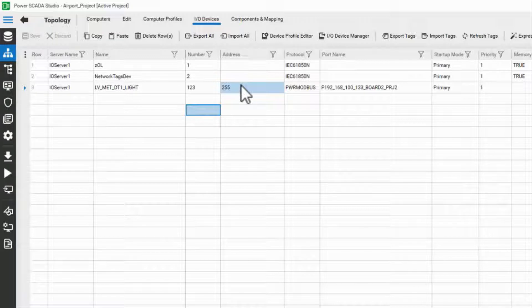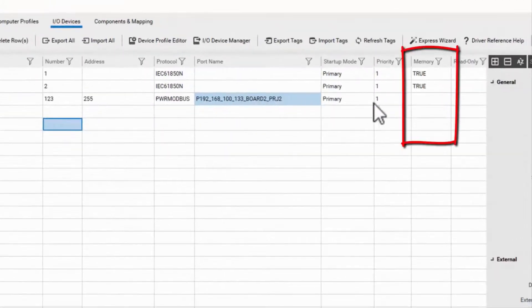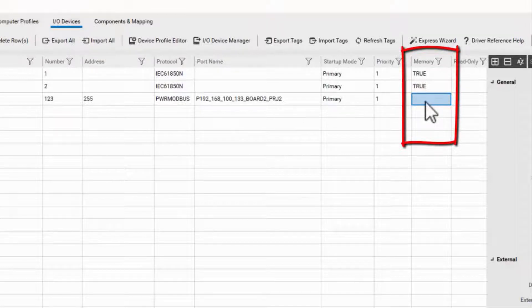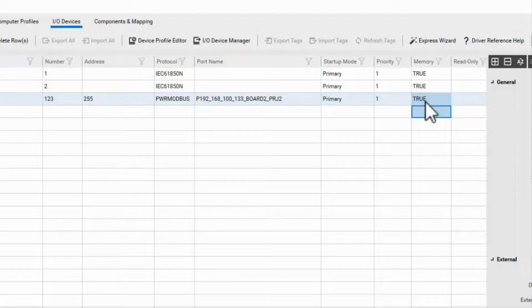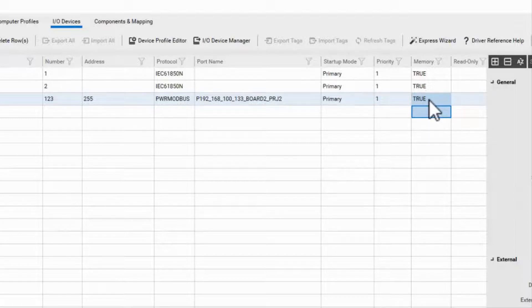I say this as a warning that finding a device's address from the databases may take some hunting. In an upcoming video, I'll show you my preferred method to keep track of the devices. The other reason to bring you here is for this memory field. If I set this to true, the device will be put into memory mode, meaning the runtime will not attempt to communicate to the field device and will not throw a communications failure alarm. I can write my own values to the memory mode device, making this field invaluable for testing. That does come with its own warning when restoring a project — if you aren't reading real data, make sure your devices aren't in memory mode.